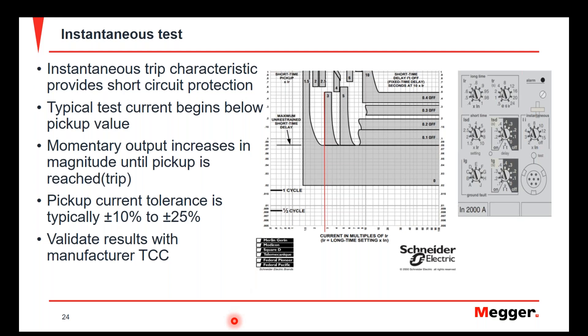The instantaneous test is a little different from the previous two. It's a pickup test performed using a momentary current output. We start below our pickup point for the instantaneous setting, then pulse current in increasing magnitudes until the breaker trips. That is the pickup point, and we record the current value at which the breaker tripped. Typically, that current value is within plus or minus 10% of the pickup value for many electronic trip unit breakers. For older-style molded-case breakers, that tolerance could be as much as plus or minus 25%.